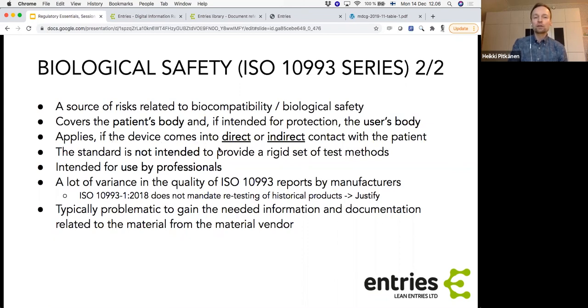This applies to devices that come into direct or indirect contact with the patient, and indirect might mean that it's a flow of fluids, for example, that goes through a tubing, and the tube then needs to be considered an indirect contact with the patient. And it's not a rigid set of test methods. You should approach any standard in the same way: this is not everything you need to do, but you need to use your own head as well to add on anything important that is missing, or interpret the requirements from your device's perspective.